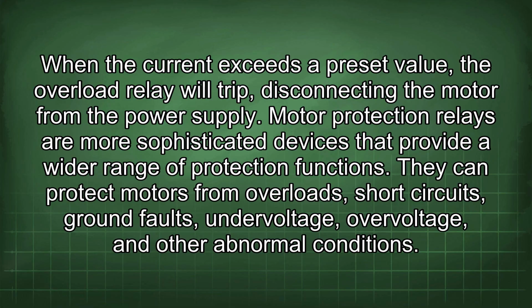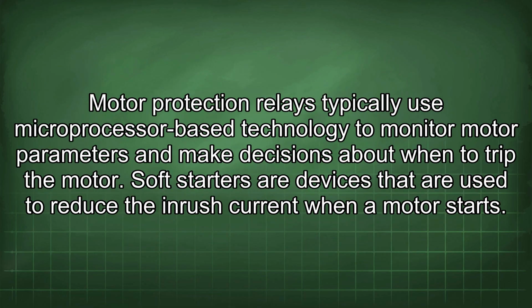Motor protection relays are more sophisticated devices that provide a wider range of protection functions. They can protect motors from overloads, short circuits, ground faults, undervoltage, overvoltage, and other abnormal conditions. Motor protection relays typically use microprocessor-based technology to monitor motor parameters and make decisions about when to trip the motor. Soft starters are devices that are used to reduce the inrush current when a motor starts.